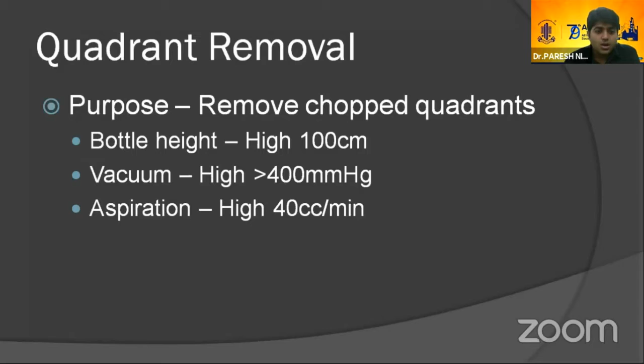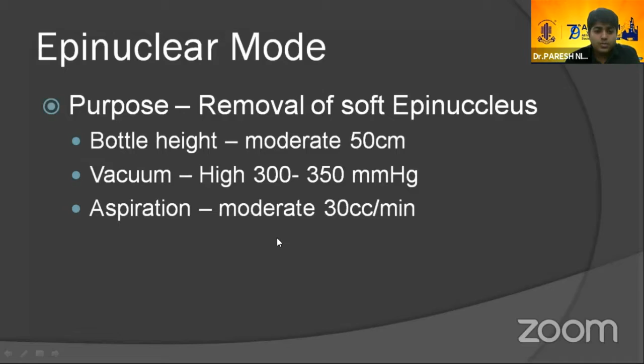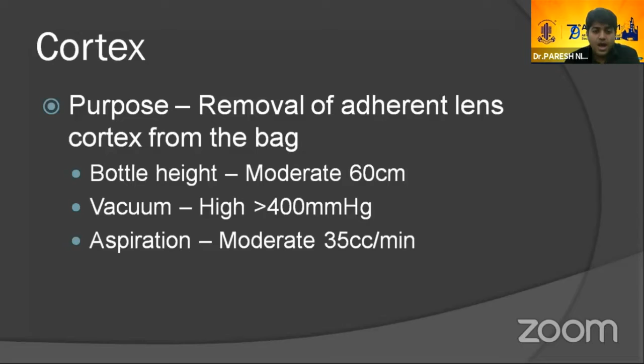In epinuclear mode, we have to remove the soft epinucleus, but keeping in mind we should not touch the posterior capsule. So bottle height should be moderate and aspiration should be moderate, whereas vacuum, because we have to hold and aspirate, the vacuum should be slightly higher. In cortex removal, the purpose is to remove the adherent lens cortex from the bag. So the vacuum should be high. We also have to keep in mind the port size of the aspiration port in irrigation IA probe is very small. So we have to keep a high vacuum. Bottle height should be moderate and aspiration rate should also be moderate.